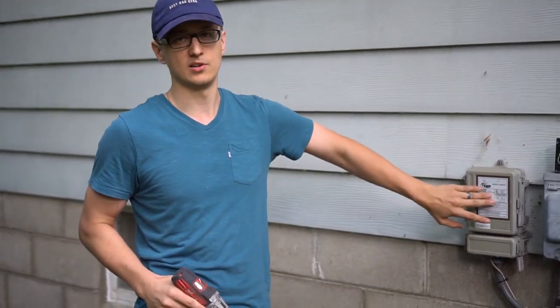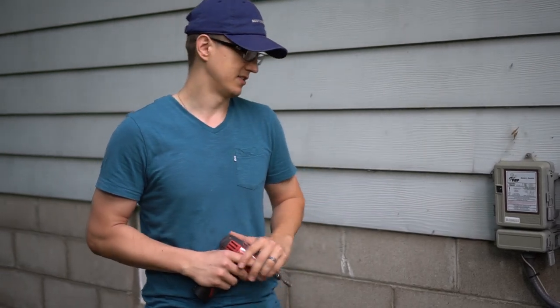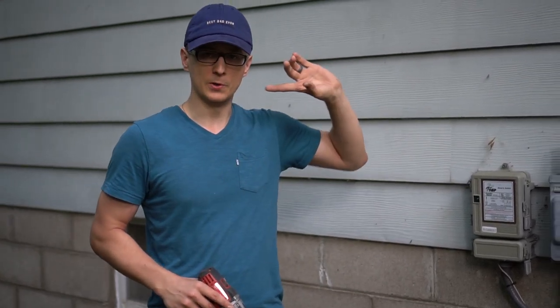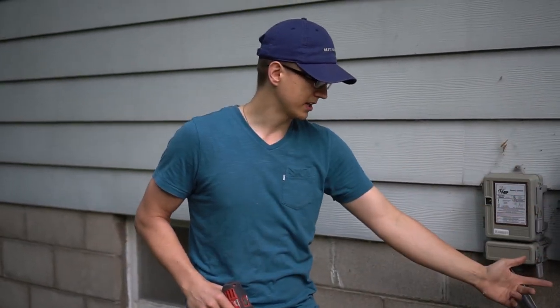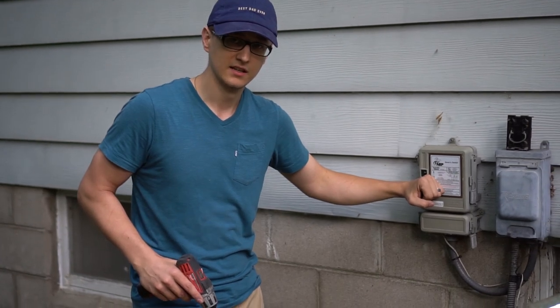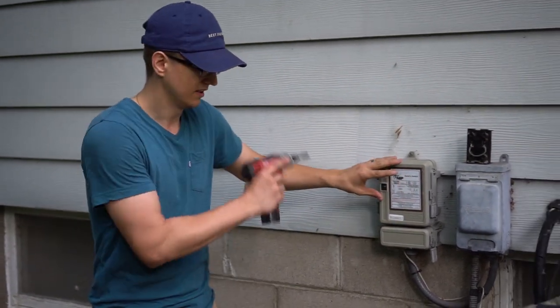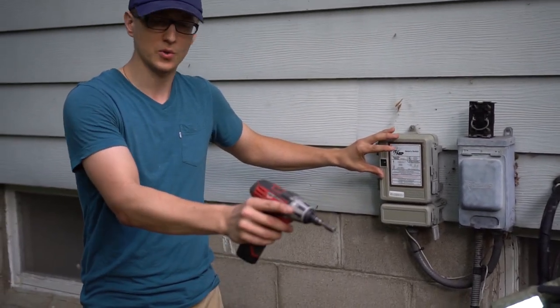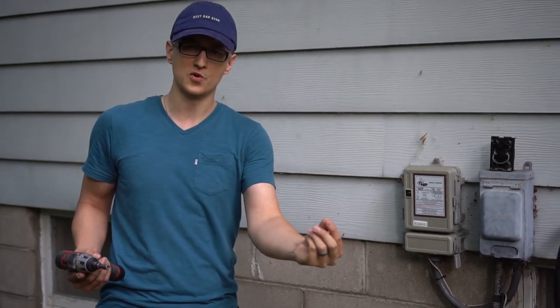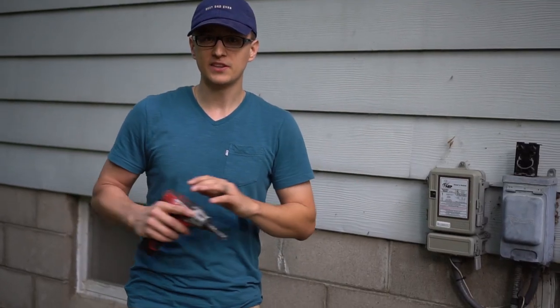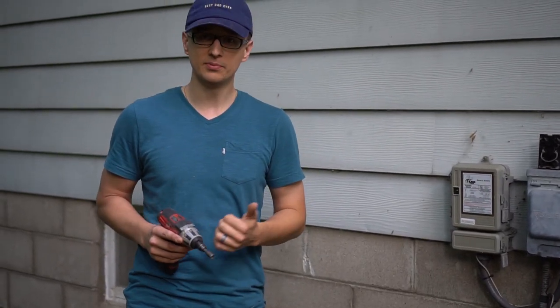Usually they'll give you some kind of discount every month for having this thing installed. But sometimes what will happen is the voltage coming in from your furnace control board will come out here, go into this thing, but because it is defective, it'll not come back out and go into your condenser unit. Therefore, your contactor plunger will not pull in.